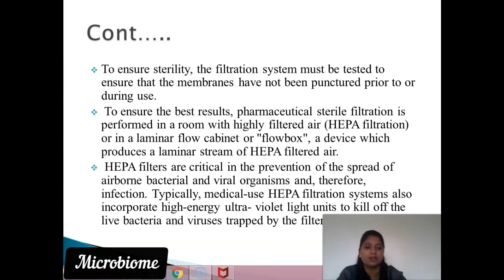HEPA filters are critical in the prevention of the spread of airborne bacterial and viral organisms and therefore infections. Typically, medical use HEPA filtration systems also incorporate high energy ultraviolet light units to kill off the live bacteria and viruses trapped by the filtration media. So when we use HEPA filters in the laminar airflow unit, there is also provision of ultraviolet light. When bacterial cells or viruses get trapped through the filtration technique, they are killed by the high energy ultraviolet lights, and that's why we get a contaminant-free area.